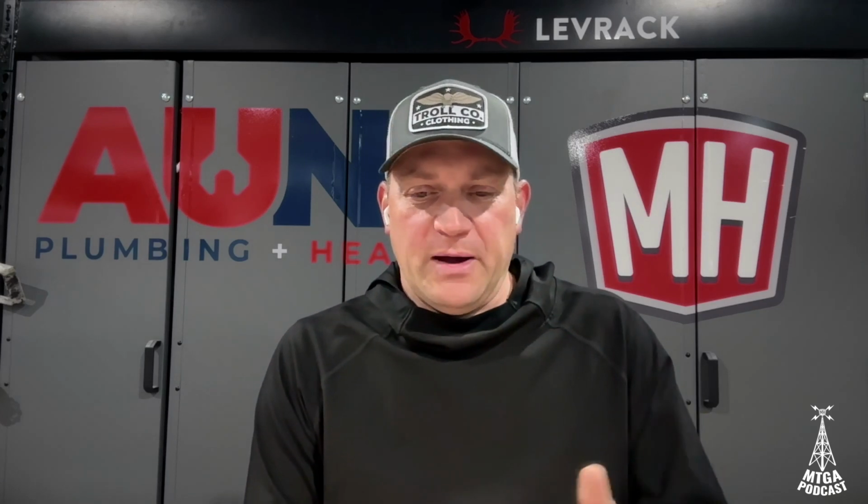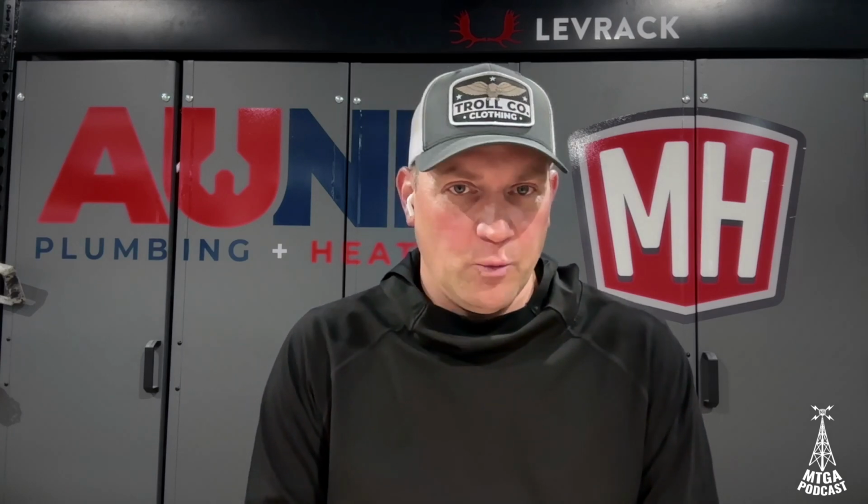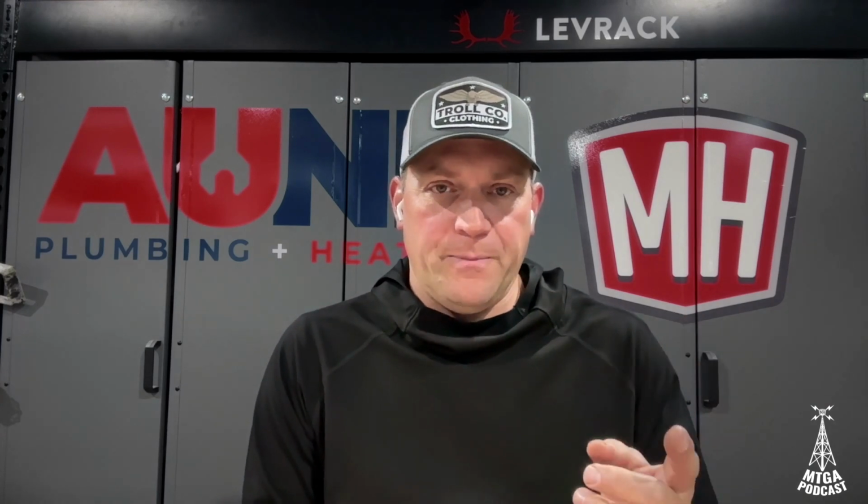But when you got that installed, you went through the wall from inside the basement. You went out to the outdoor unit. You were still full size 1.25 inches, correct? Yep. We transitioned over. What I wanted to do is make sure that where we went from the house to the unit, there was some PEX extending out of the house, mostly just for vibration. So we extended that PEX outside the house. It came out, I don't know, 8 or 9 inches with the 1.25 inches. We transitioned down to 1 inch and then went as quickly as possible into 1 inch copper. Then we ran that 1 inch copper up and into the unit.